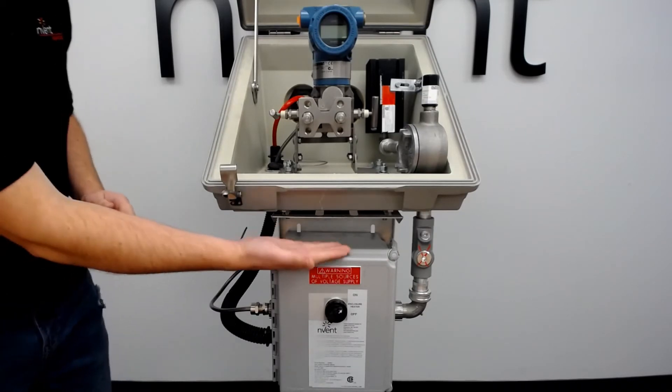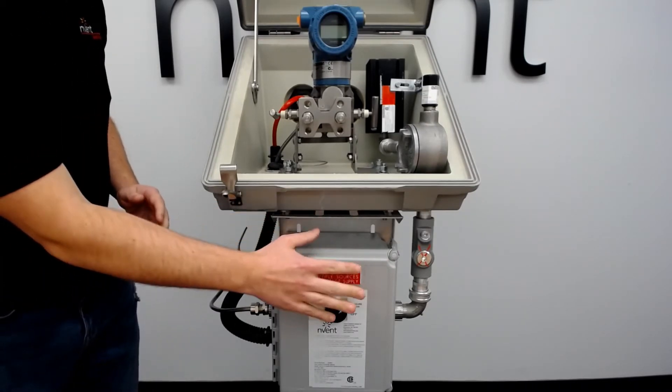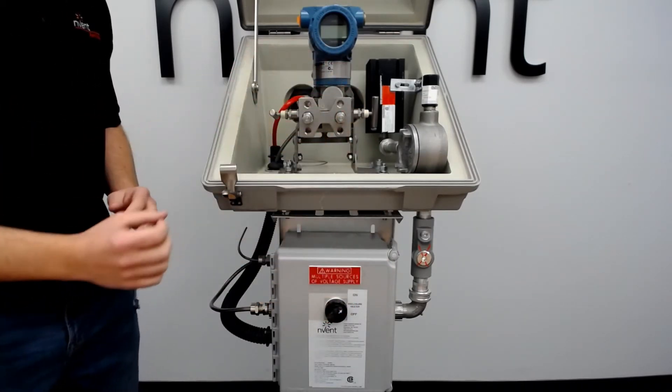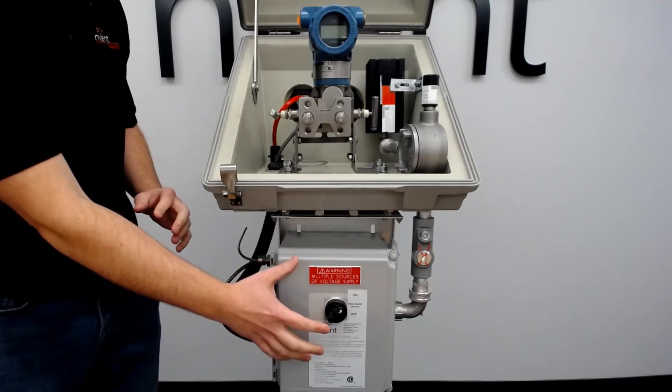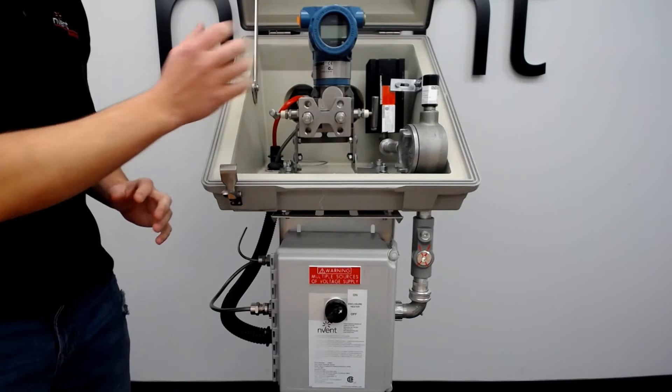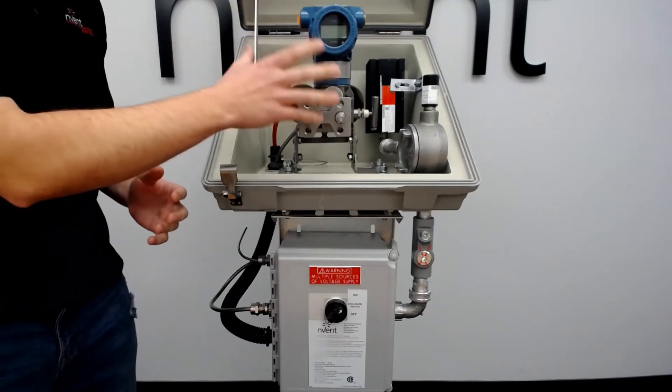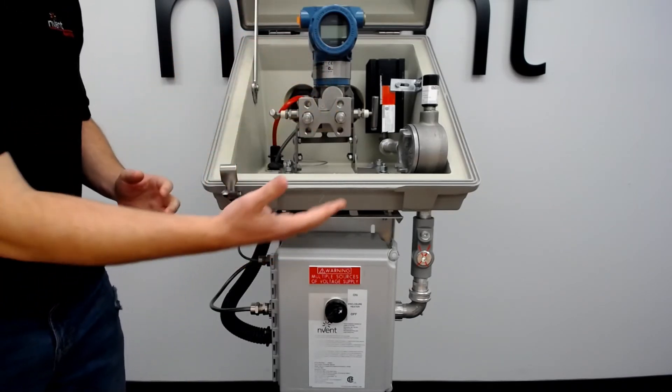As you can tell, there is physical separation between the junction box and the enclosure. That's because the junction box is typically a Div 2/Zone 2 rating, whereas the enclosure is usually more stringent and is Div 1 or Zone 1, so there has to be physical separation.